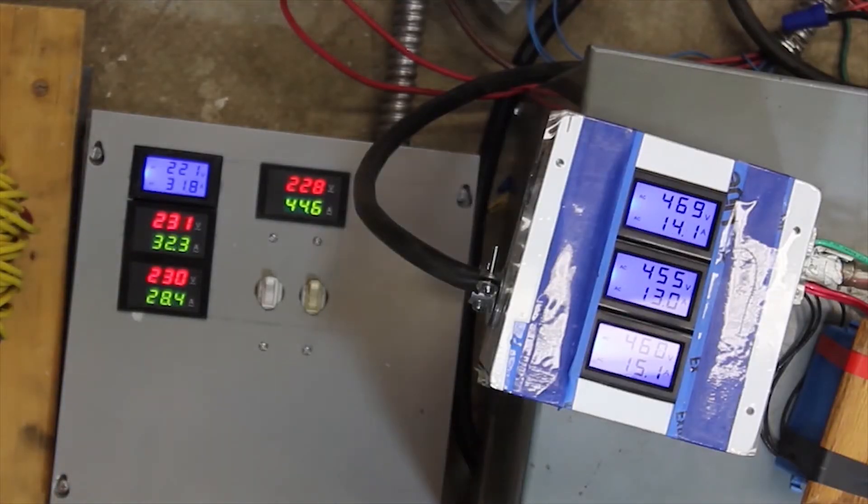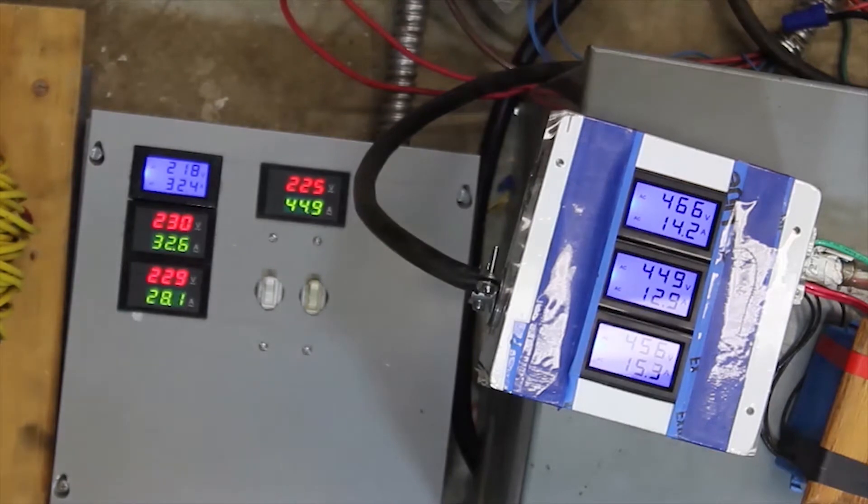Take a look at the balance on this. Here we are running this thing into the transformer, 469, 453, 459. Balance is really quite good.